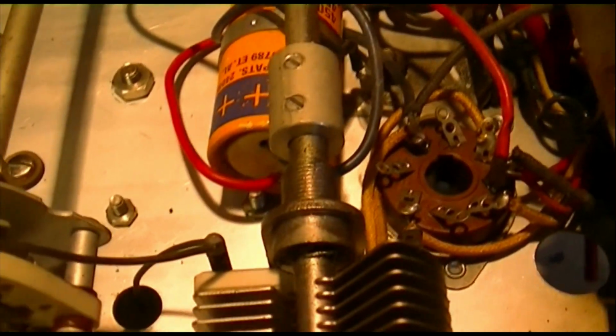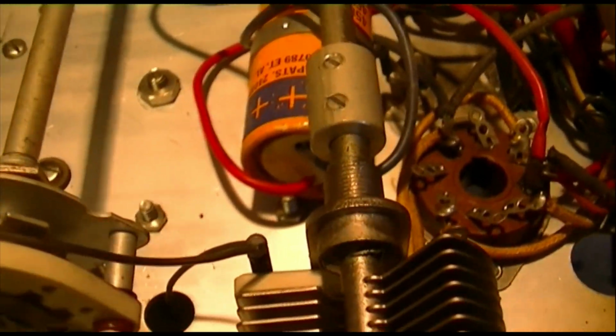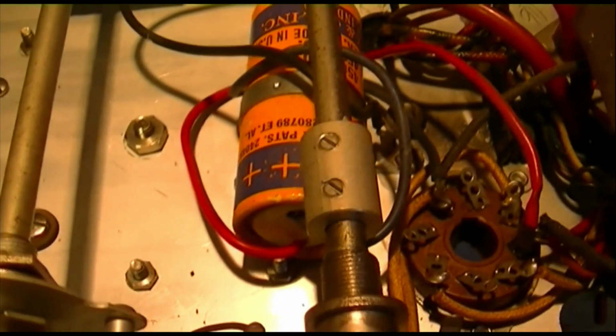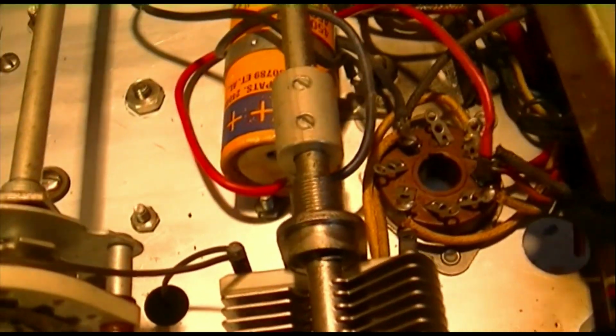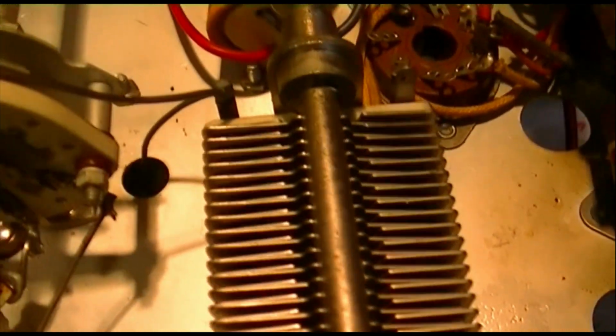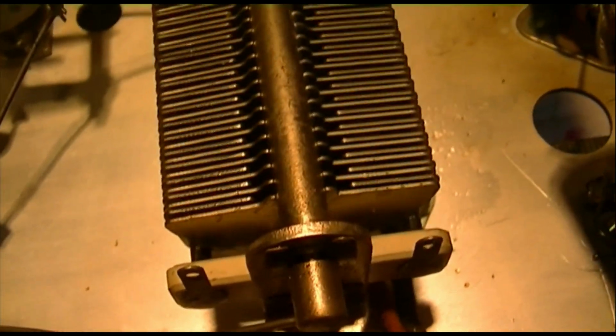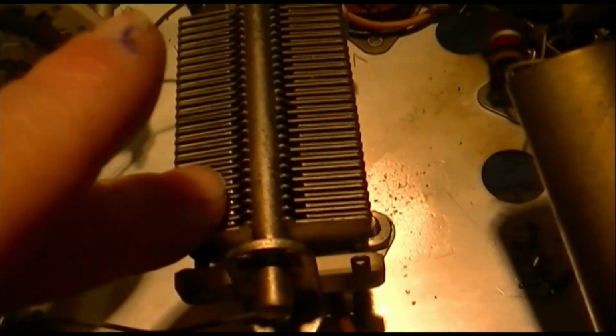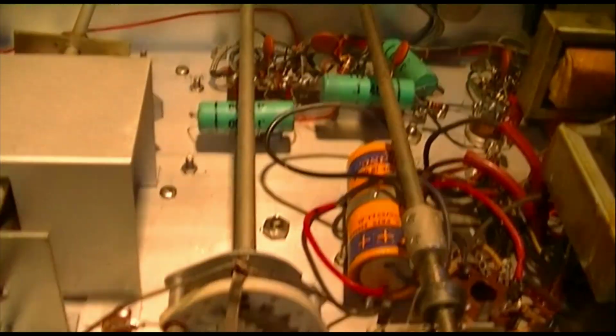While you're in here, you're going to discover stuff that's not right. Like this coupling was loose, so I had to take a screwdriver and tighten it up. While you're at it, you can zero this out and make sure the knob position is right on the panel. You can either change the knob or change the coupling, whichever is easier, but it helps to have the knobs in the right condition. When these things have been loose, they can get screwy.